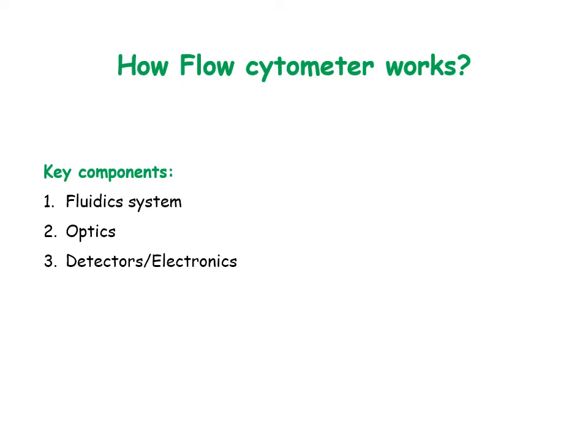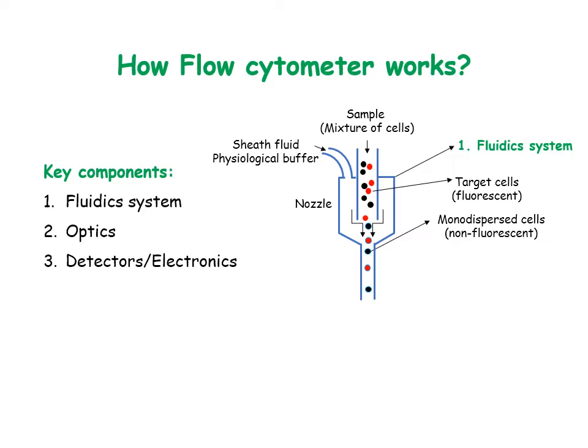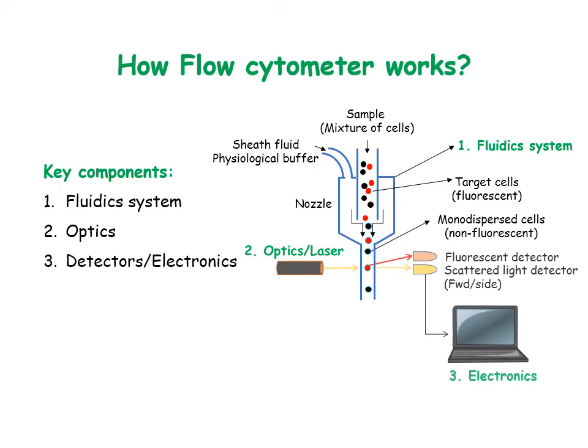A flow cytometer comprises three components: a fluidic system that forms a monodispersed stream of cells so that just one cell passes through at a time — here, the red dot represents target cells expressing red fluorescence and the black dot represents non-target cells showing no fluorescence; an optic system like a laser for excitation of fluorescent cells; and an electronic component or detectors that detect and differentiate fluorescent signals from scattered light, converting them into digital signals for subsequent data analysis. After this, the cells are discarded.